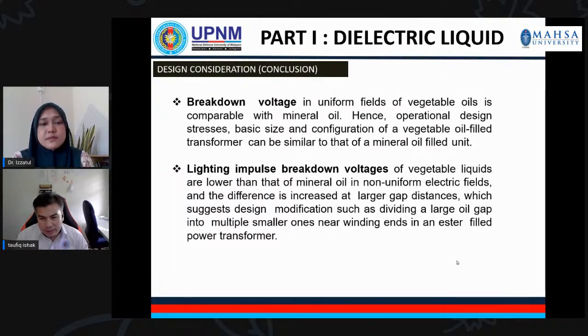In terms of lightning impulse breakdown voltage, the vegetable oil is lower than mineral oil. You can see from the result, especially in a non-uniform electric field, and the difference increases especially at the larger gap. So what we can suggest is a design modification: we need to divide a large oil gap into smaller oil gaps, especially near the winding end when you are using an ester filled power transformer. So you need to do some modification in your design, especially in the area where you have a larger gap distance. You have to make it a smaller gap distance inside the larger gap area, so that you can avoid a small breakdown voltage as compared to a larger gap distance. That's the recommendation in terms of lightning impulse breakdown voltage.